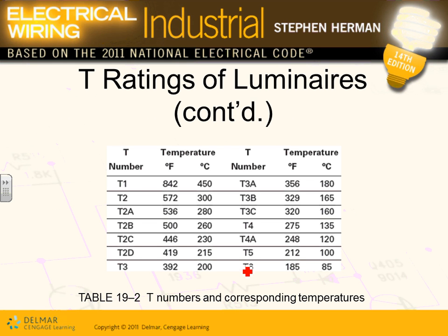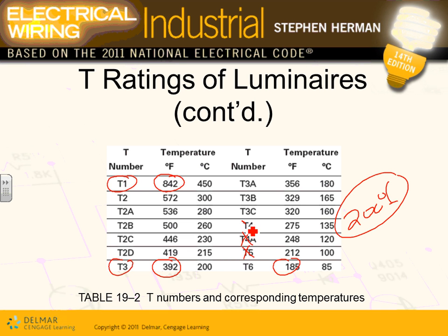Look at this, if it says T1, the operating temperature of T1 is 842 degrees Fahrenheit. Operating temperature of T3 is 392 Fahrenheit. Operating temperature of T6 is 185 degrees Fahrenheit. So if you have a gas that can ignite at 200, the ignition temperature is 200 for this gas, I can't use any of these. I have to use T6, because T6 can't get hotter than 185. And the gas can be ignited at 200, so I am below the ignition temperature of that gas.